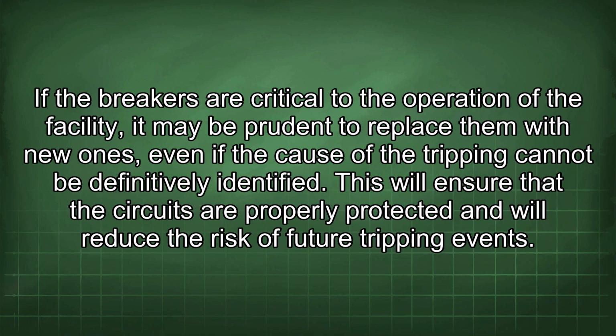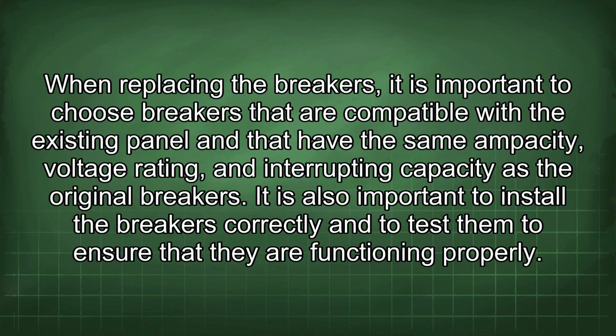If the breakers are critical to the operation of the facility, it may be prudent to replace them with new ones, even if the cause of the tripping cannot be definitively identified. This will ensure that the circuits are properly protected and will reduce the risk of future tripping events. When replacing the breakers, it is important to choose breakers that are compatible with the existing panel and that have the same ampacity, voltage rating, and interrupting capacity as the original breakers. It is also important to install the breakers correctly and to test them to ensure that they are functioning properly.